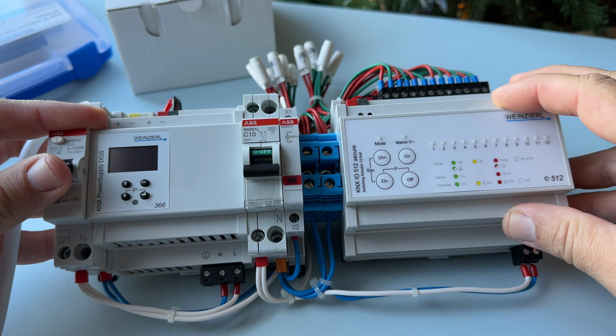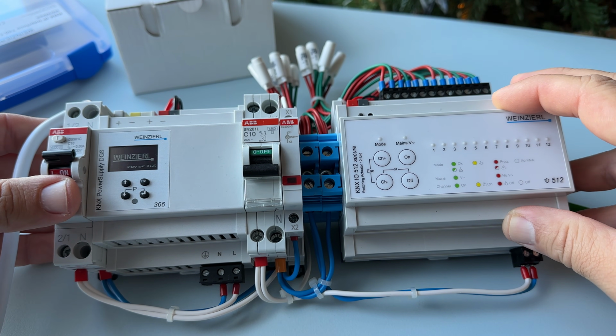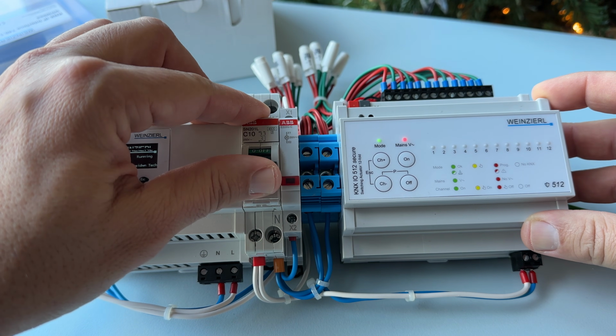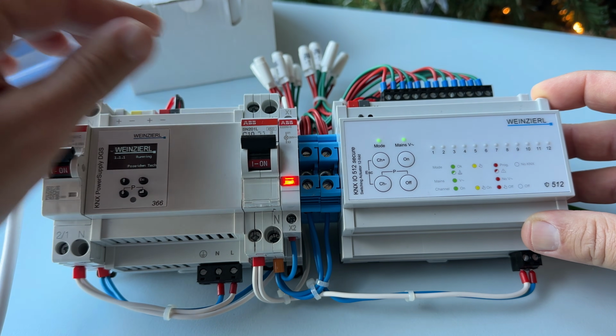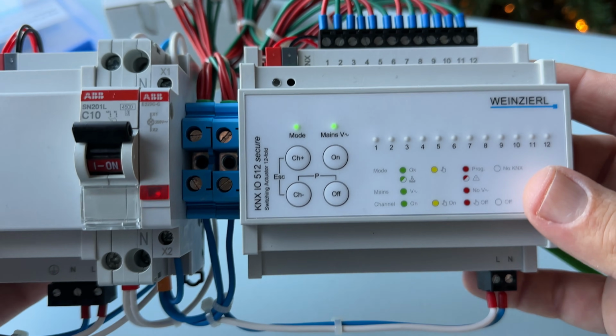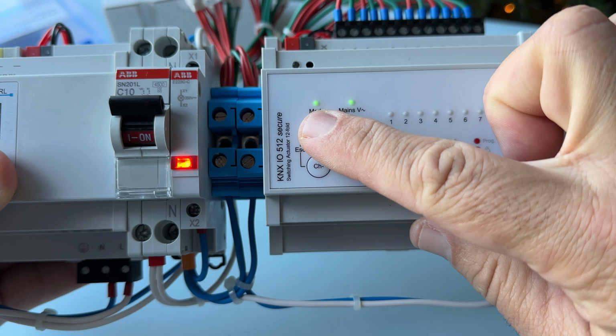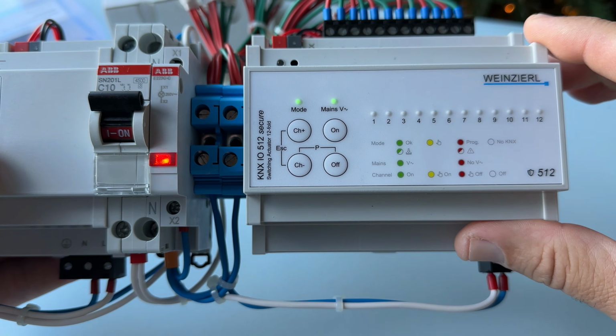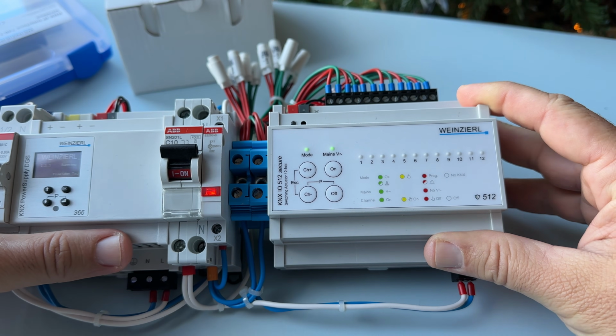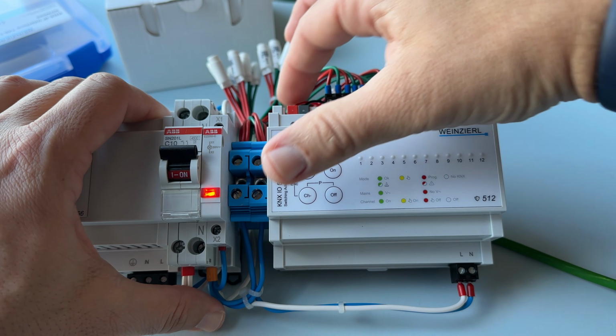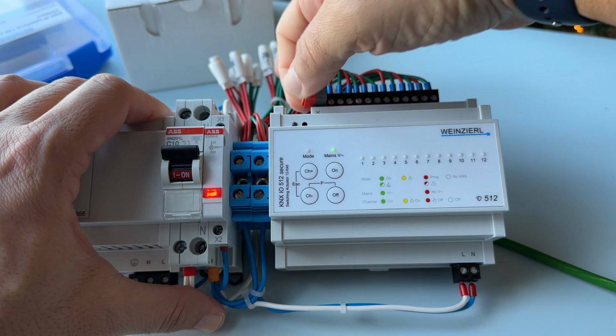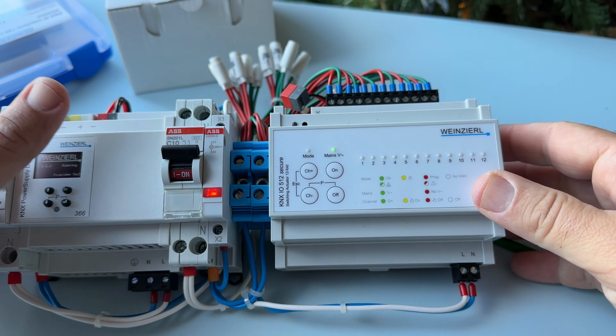I'll turn on the KNX power supply and provide line and neutral to the switching actuator. As you can see, the mode and mains LEDs turn green, indicating normal operation. Let's try manual control first. This can be done even without a KNX bus connection, which is very helpful for testing your installation.